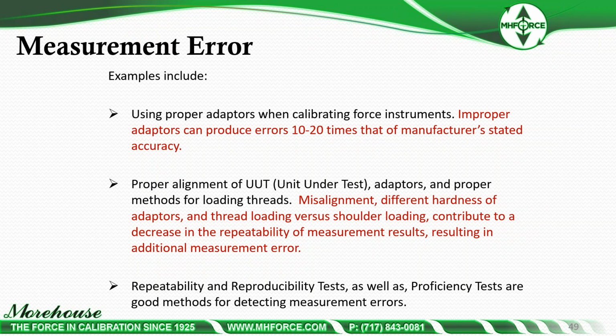Proper alignment of the UUT, unit under test, adapters, and proper methods for loading: threads, misalignment, different hardness of adapters, thread loading versus shoulder loading, all contribute to a decrease in the repeatability of the measurement results, resulting in additional measurement error. Repeatability and reproducibility tests, as well as proficiency tests, are good methods for detecting additional measurement errors.